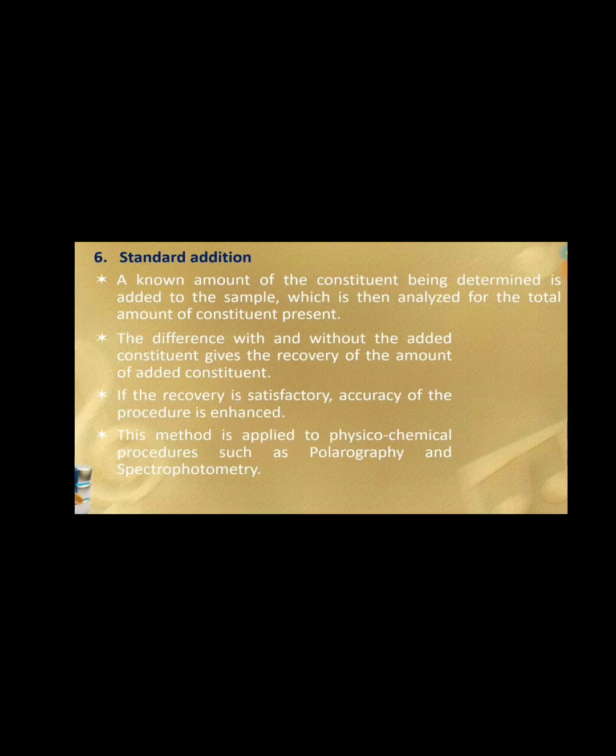Then sixth one, standard addition. A known amount of the constituent being determined is added to the sample, which is then analyzed for the total amount of constituent present. The difference with and without the added constituent gives the recovery of the amount of added constituent. If the recovery is satisfactory, accuracy of the procedure is enhanced. This method is applied to physicochemical procedures such as polarography and spectrophotometry.